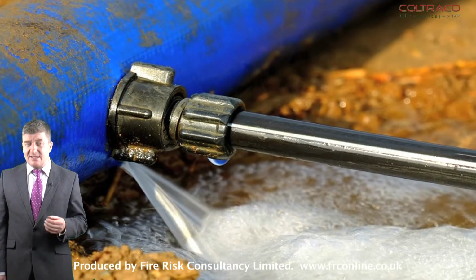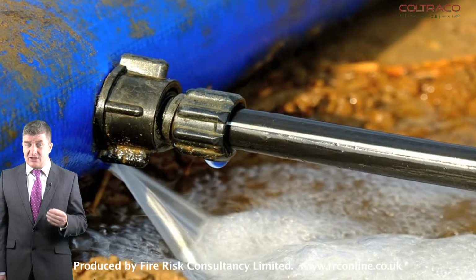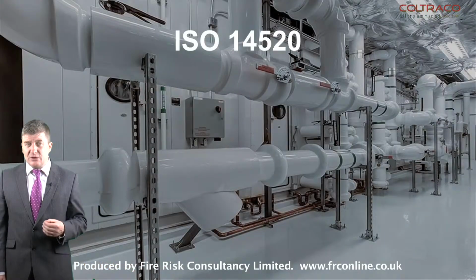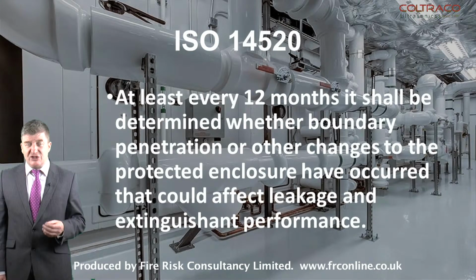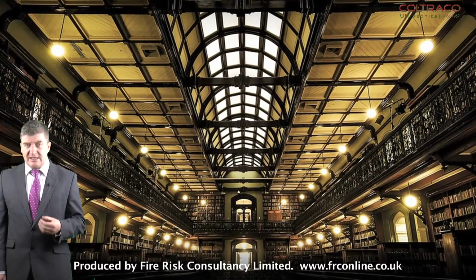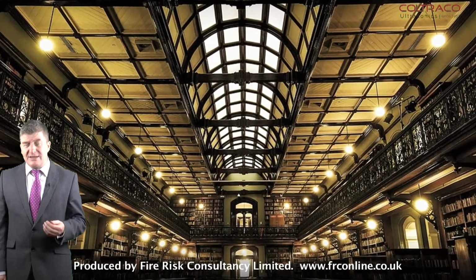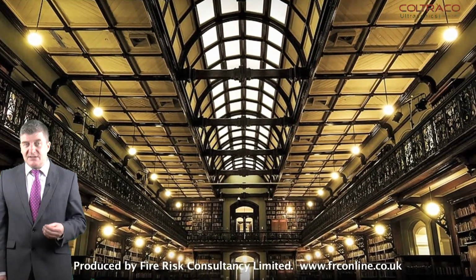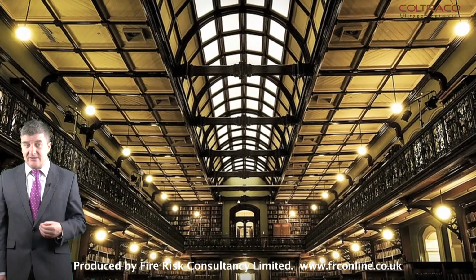Now, the risks of accidental discharge or leakage is also recognised, and this comes under the room or protected space enclosure, which states that at least every 12 months it shall be determined whether boundary penetration or other changes to the protected enclosure have occurred that could affect leakage and extinguishant performance. Now, if this cannot be visually determined, it shall be positively established by repeating the test for enclosure integrity.